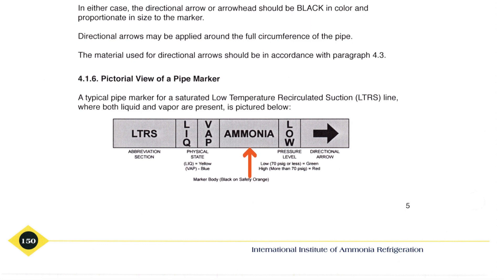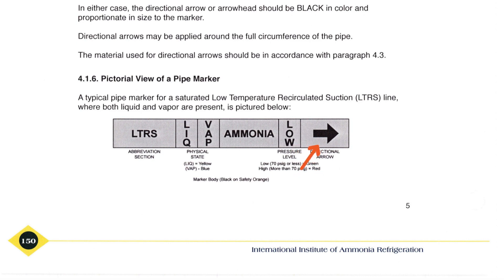Required pipe labels per IIAR Standard 2 include: the word "ammonia" printed in black letters; the physical state abbreviation — LIQ or VAP; the relative pressure — high or low; an arrow depicting the direction of flow in the pipe; and a service abbreviation indicating the purpose of the pipe.